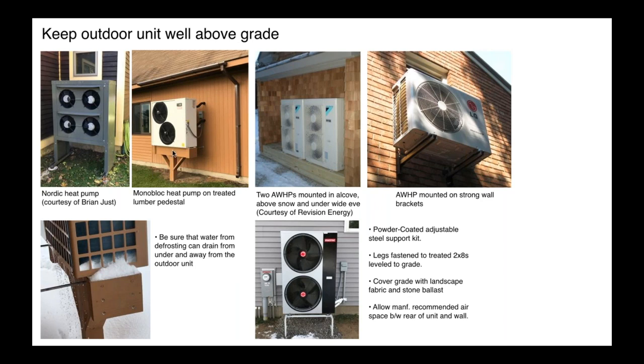Here's a single pressure-treated pedestal that supports that unit. Here's a couple units that actually has an alcove. This was new construction. So they built an alcove here, and you can see both units are running in parallel. They're a few inches up in this area where the snow cover doesn't get above them. It is important you get airspace behind these units. Don't push these units right up against the wall. Most of the manufacturers want to see at least a foot, sometimes maybe a foot and a half behind the unit to make sure that you aren't restricting airflow that is basically from back to front on these units. In some small capacity equipment, you might be able to use wall brackets to mount the unit like this.